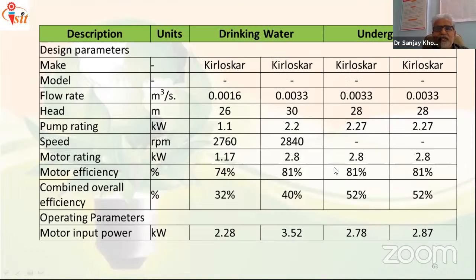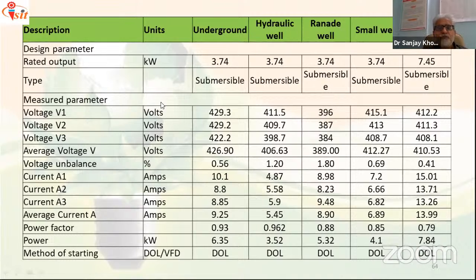So like this we prepare for the drinking water also. Now here there are different types of pumps. Suppose this data is taken from the nameplate. Here the flow is meter cube per second, 0.0016. Head, how much it is for that particular application. Pump rating, speed of the pump, motor rating, motor efficiency, combined overall efficiency, because it is motor plus pump, and motor input power. Now here you can see this is 2.28, the motor input power, and we'll see what happens after replacement. Similarly for the different types of pumps, we have gathered all this information.